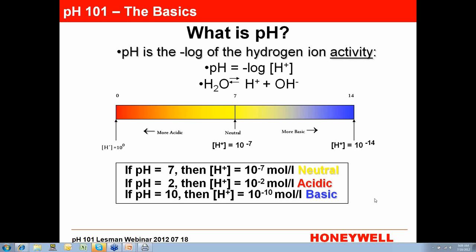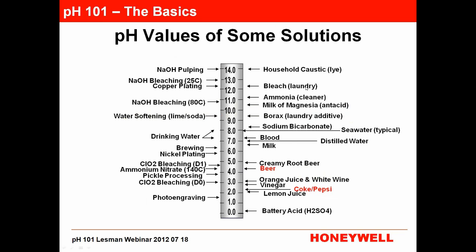The negative log of hydrogen ion concentration means we're just counting hydrogen ions in the process — that's all a pH sensor does. The pH scale is 0 to 14, more or less. If you're at a pH of 7, you have 10 to the minus 7 moles per liter of hydrogen ion. That's a neutral pH. If you're at pH of 2, then you have 10 to the minus 2 moles per liter. pH is a log function — it's not linear — and that's why it can be very difficult to control, because it gets away from you pretty easily.